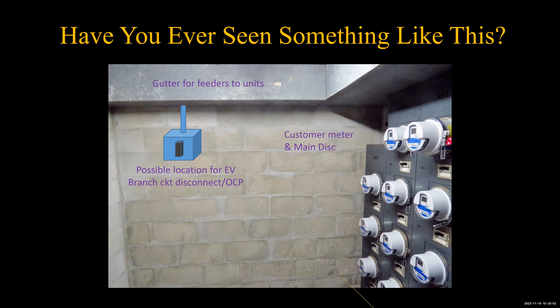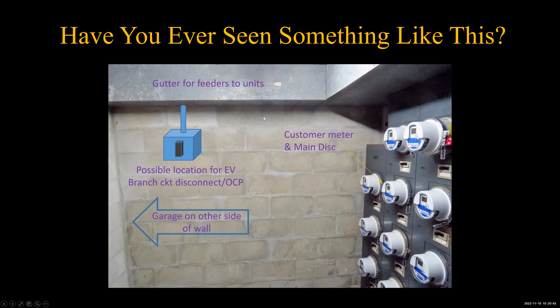And you feed from there, and there's your customer meter and main disconnect right under it. And out there on the other side of that wall, there's the garage. So you may have to go 50 or 100 feet along the garage wall, making careful that you don't have a ceiling that has post-tension cables in it, because you don't want to mess with drilling into a ceiling with post-tension cables unless you've got a mighty fine X-ray machine or ultrasound machine to find where those cables are. And unless you're willing to pay somebody who will certify that they are in the right place, maybe you're able to certify them yourself. If so, that's fine, but that's the issue.